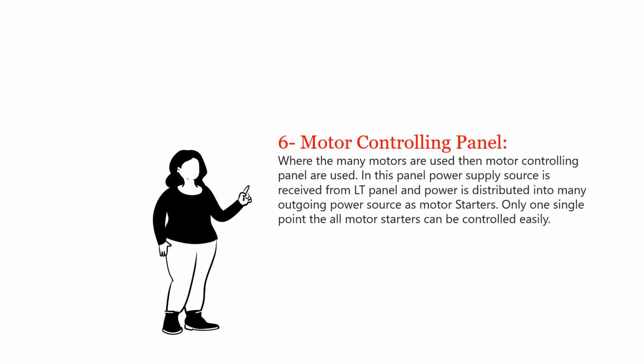Motor controlling panel. Where many motors are used, motor controlling panels are used. In this panel, power supply is received from LT panel and power is distributed into many outgoing power sources as motor starters. From only one single point, all the motor starters can be controlled easily.